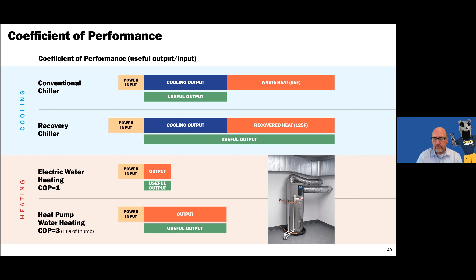The coefficient of performance, the COP, means higher energy efficiency. And when we have heat recovery chillers with a high COP, it includes both the cooling and the heating energy. And in the COP for heat pumps in mid-Southern California climate, the rule of thumb is about 3, one unit of energy input and 3 units of energy output. And this little picture here just shows the ductwork to outside ambient air, and we've used that style successfully. Go ahead, Tom.